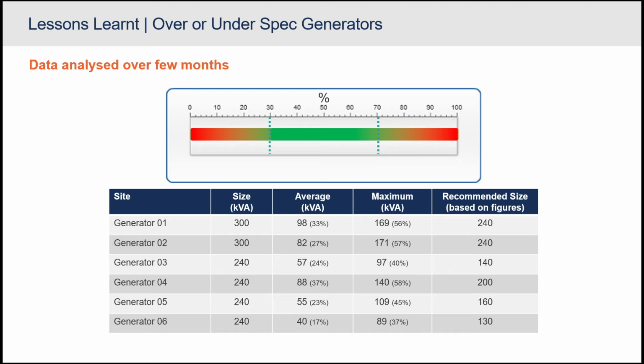So we look at this specific client that's got 6 generators. What are the sizes of it? Over a couple of months, we trended each load shedding event that it ran, what was the average power it actually used, and what was the maximum used. Once again, because we've got all the data in the system, it's quite easy to extract that.